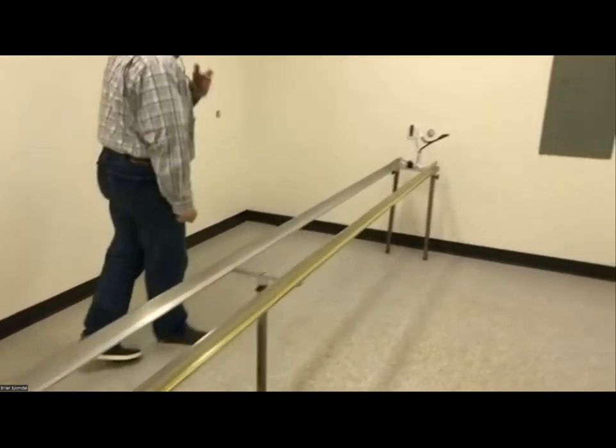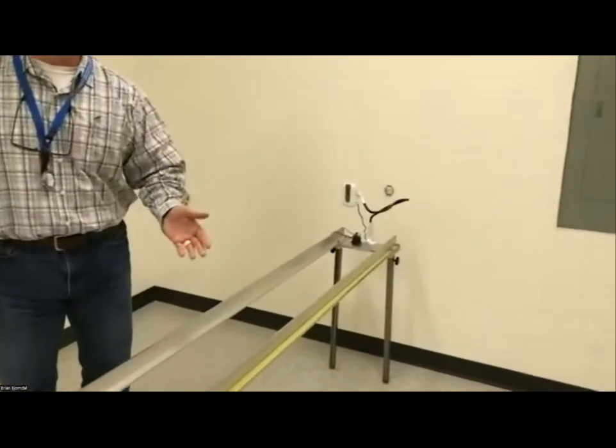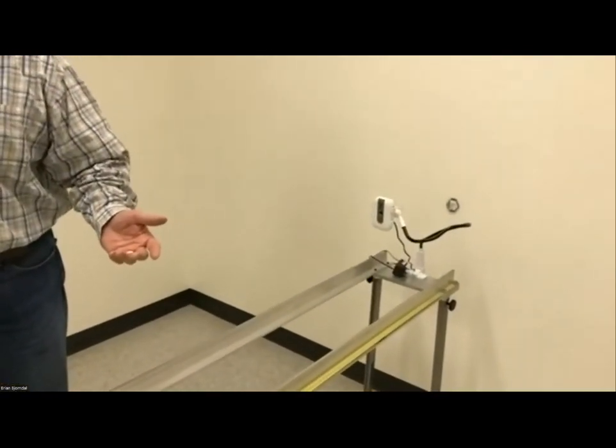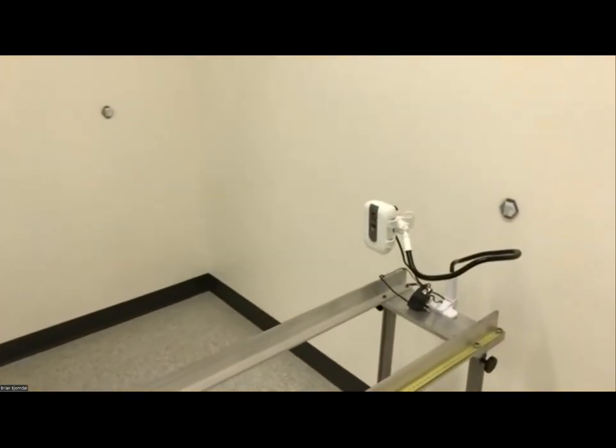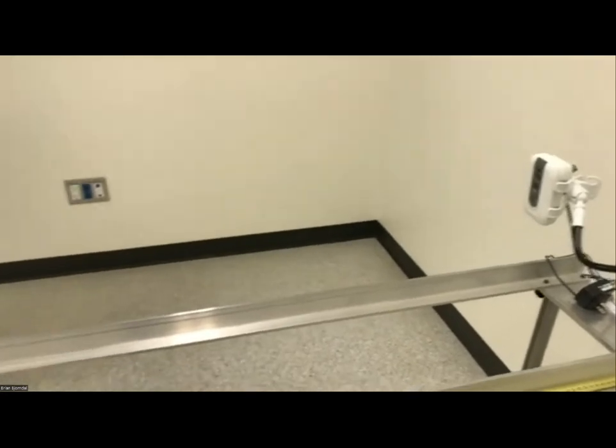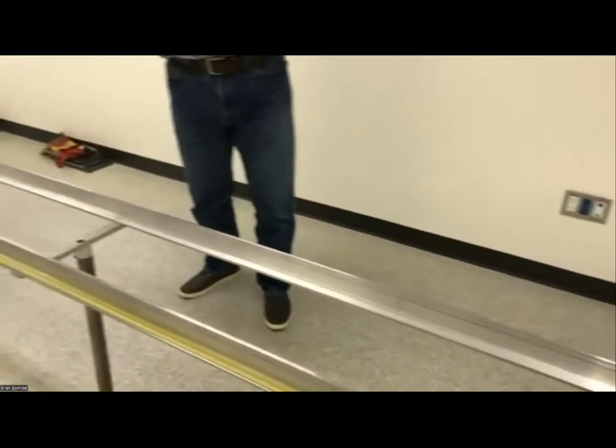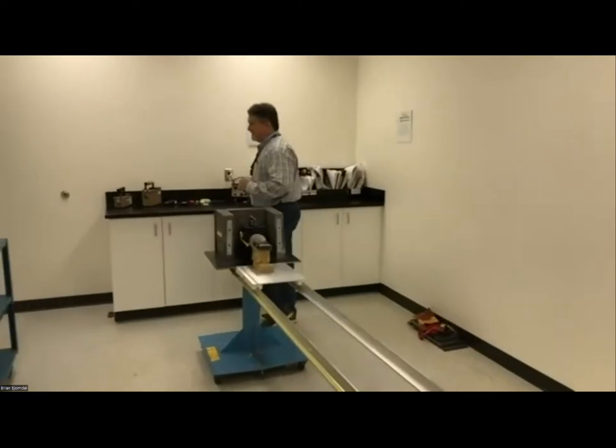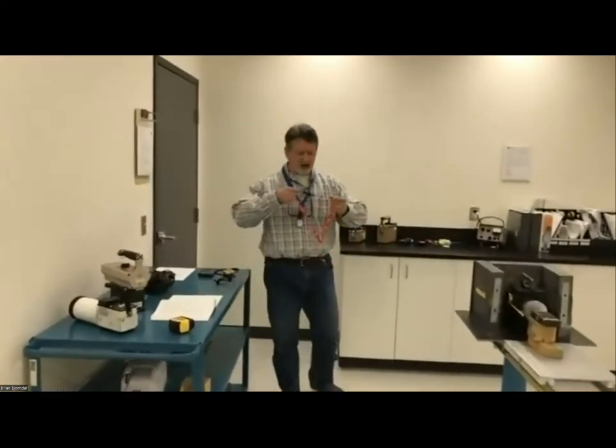We also have Wi-Fi cameras, because you can imagine if the detector's way out here, it's pretty tough for the tech to read anything off an instrument. So we can use Wi-Fi cameras to set it up and measure the dose rates. A few safety things. When we're working in here, we're always wearing dosimeter badges. We also have electronic DRDs, which the technician will wear when performing calibrations. In the event that something goes wrong, which never has, it gives us an immediate indication of dose rates around the source, and it can be set to alarm the technician that there is an issue and they need to take action. So PLDs are worn, and a DRD is worn by the technician.